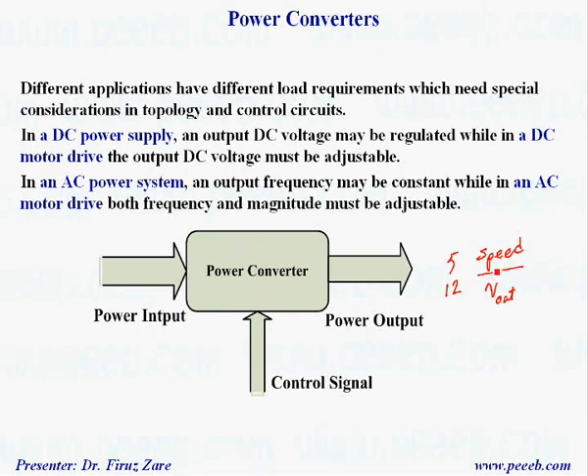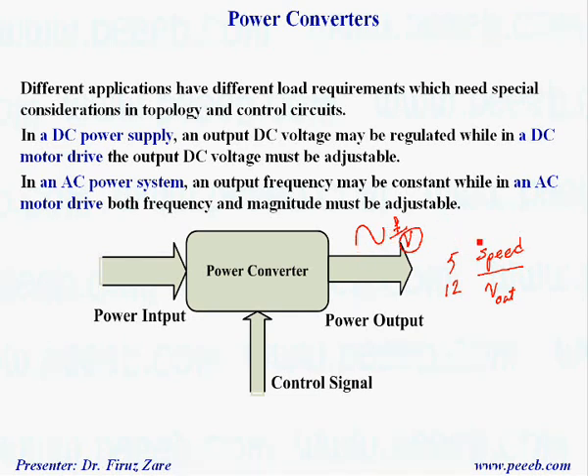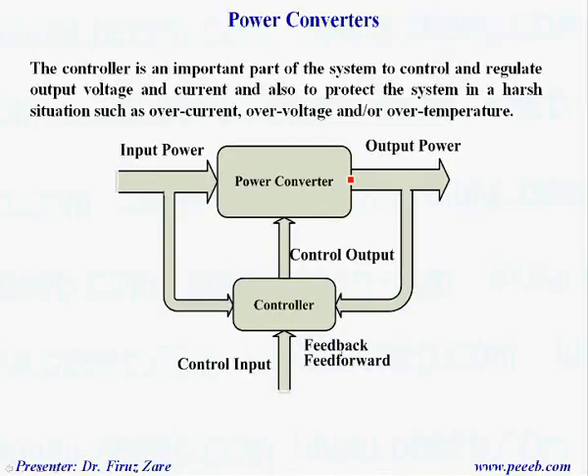In an AC power system where the output voltage should be AC, we should be able to control the frequency and magnitude. If it's an AC power system application, normally the frequency is constant and we need to control the magnitude. In an AC motor drive, we should be able to control both frequency and magnitude in order to control the speed.